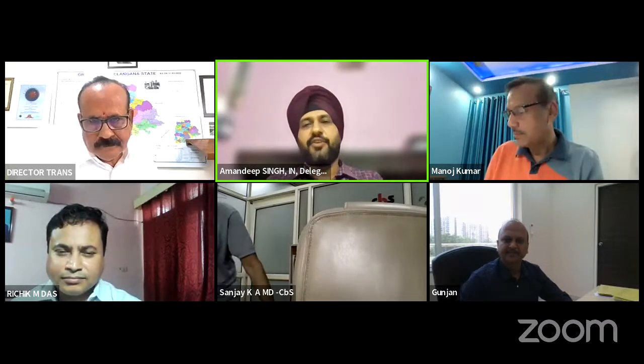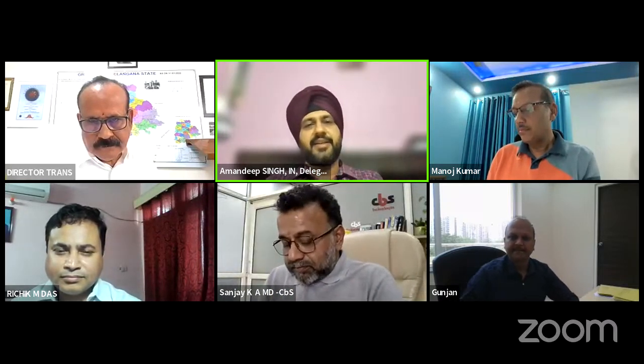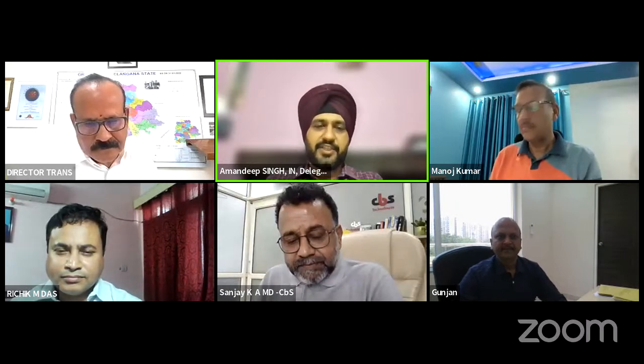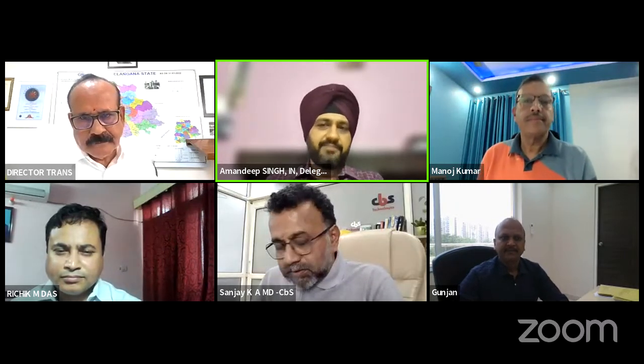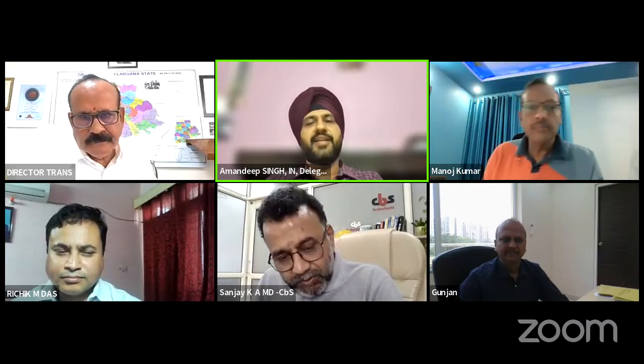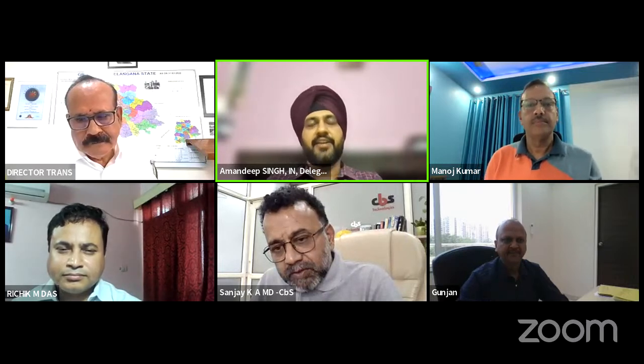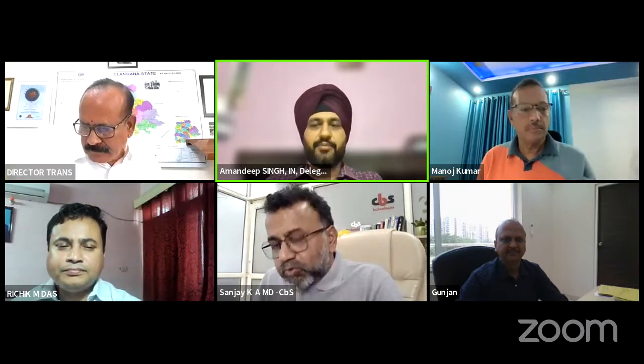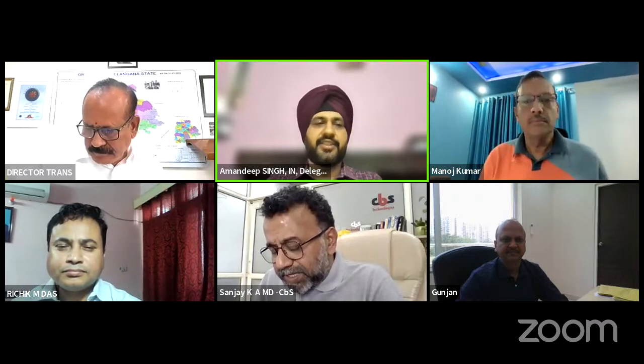I would just like to make a small submission to our partners from the Telangana team. Sir, as per CIGRE, calculation is done based on the service life period. So if you would account for that service life period, then maybe your failure rate would be more consistent. Otherwise it is appearing that at some points it is 1.14%, at others it's 0.3%.